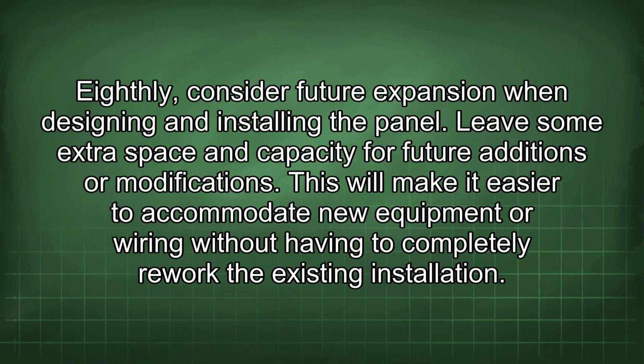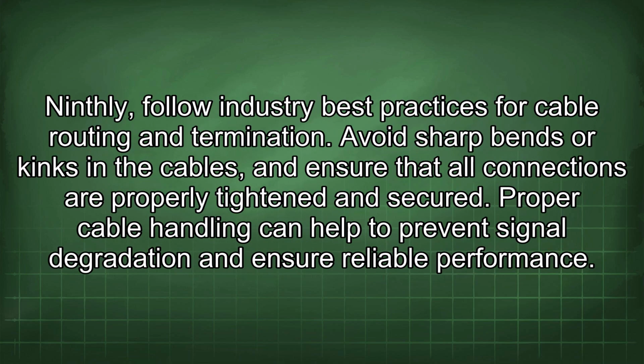Eighthly, consider future expansion when designing and installing the panel. Leave some extra space and capacity for future additions or modifications. This will make it easier to accommodate new equipment or wiring without having to completely rework the existing installation. Ninthly, follow industry best practices for cable routing and termination. Avoid sharp bends or kinks in the cables and ensure that all connections are properly tightened and secured. Proper cable handling can help to prevent signal degradation and ensure reliable performance.